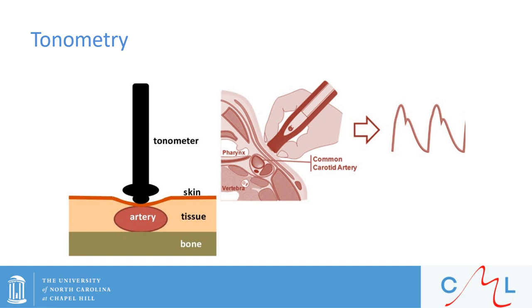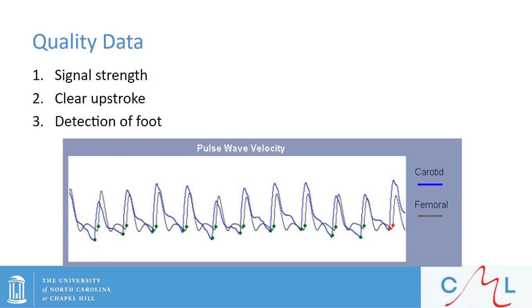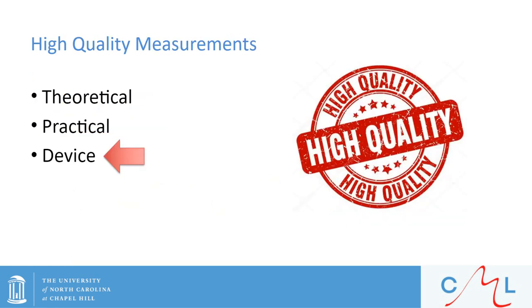With respect to anatomy, we should understand what we're actually looking for — like the carotid artery being palpated — and know what to do with that artery, why and where we're compressing it, to ensure a high quality reading. We also need to understand what a good waveform looks like in real time: look for adequate signal strength, make sure the waveform has a clear upstroke, and if the device does it, make sure it is identifying the correct foot on the waveform.